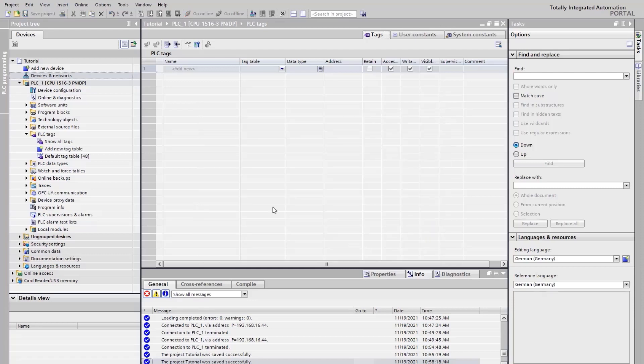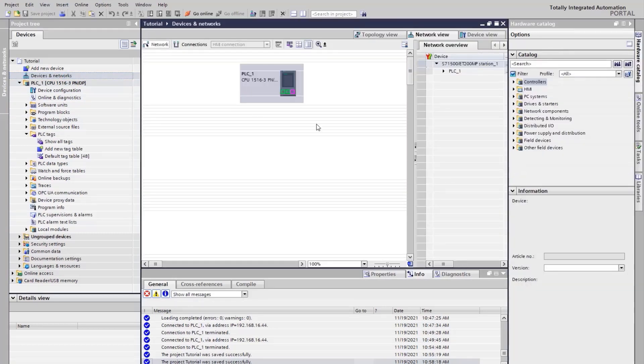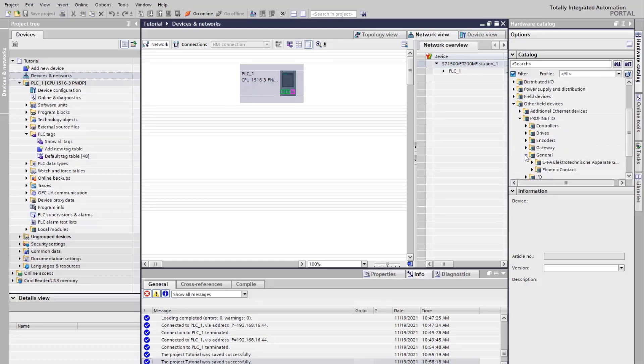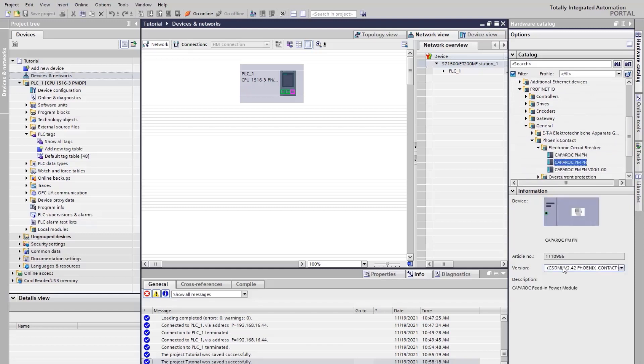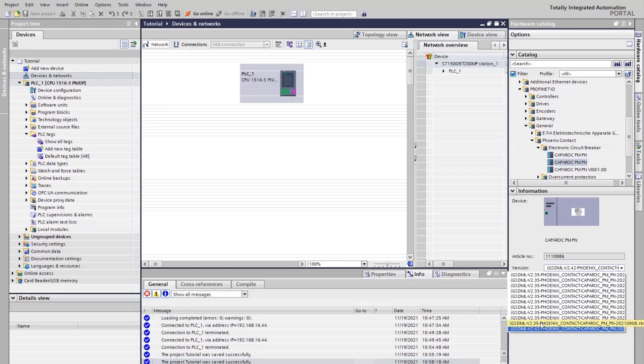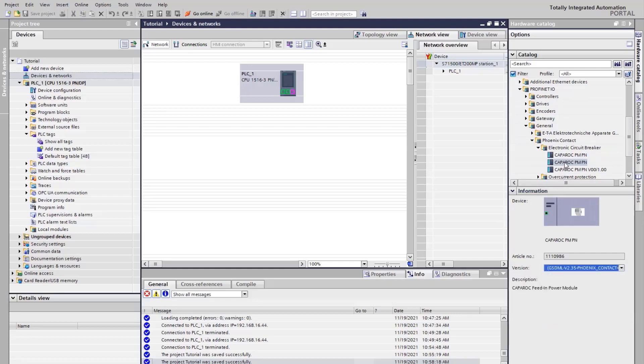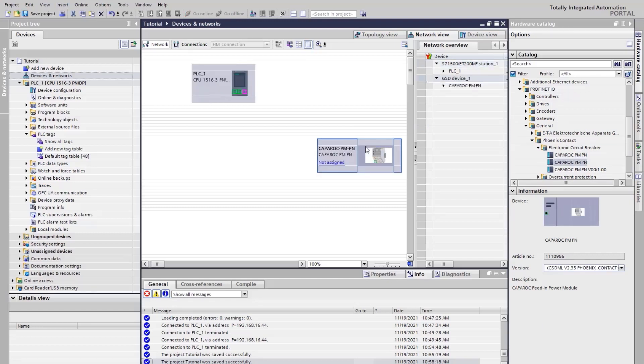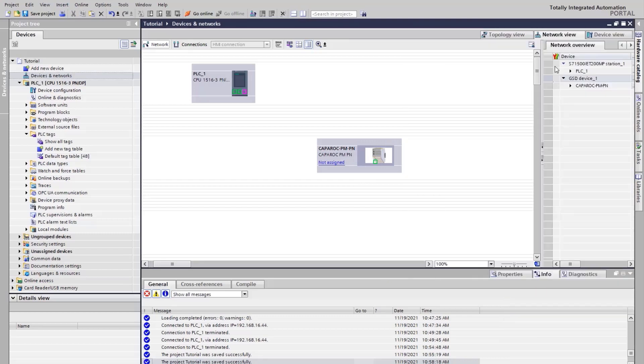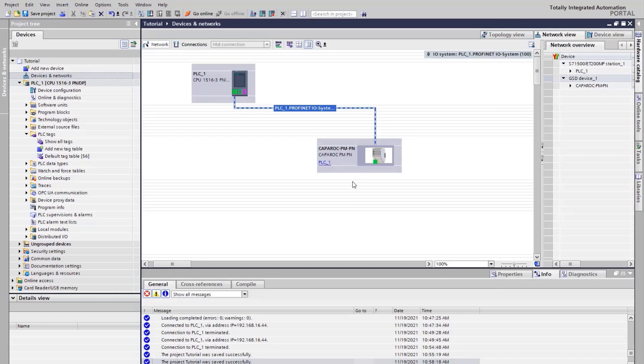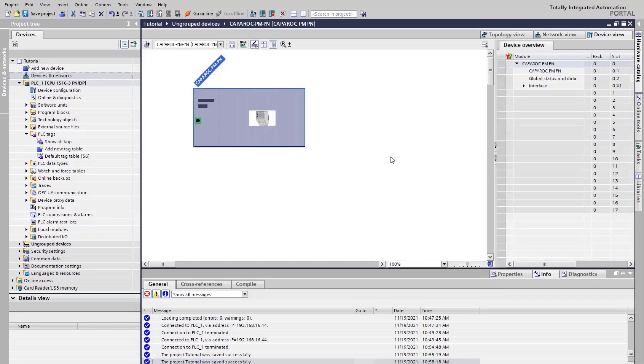Open Device and Networks and add the Caparock Power module via drag and drop to your hardware configuration. Select a PROFINET interface of the I/O controller for the Power module. Assign the IP address and PROFINET device name to the Power module.